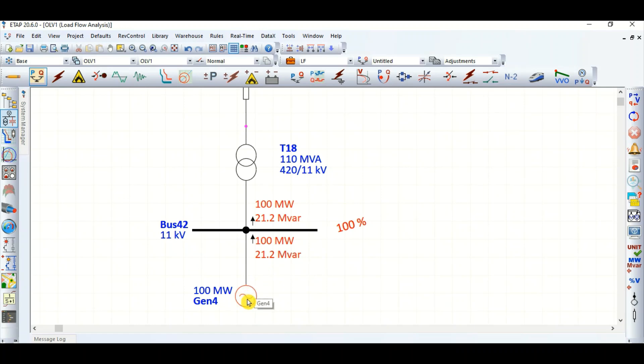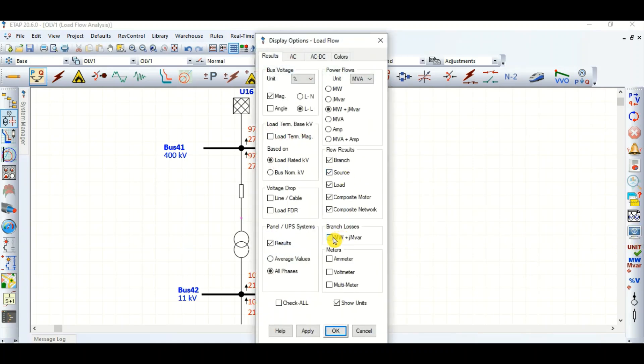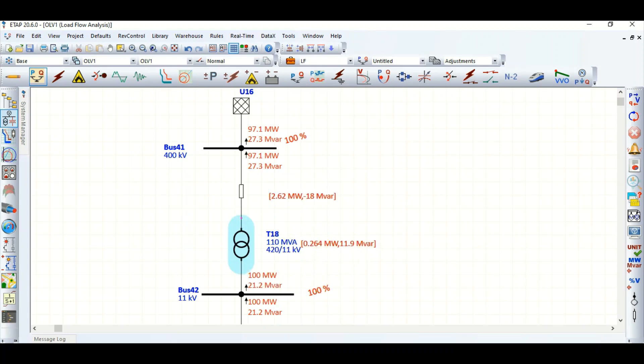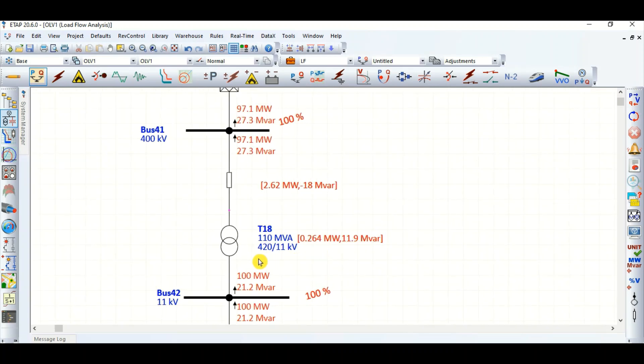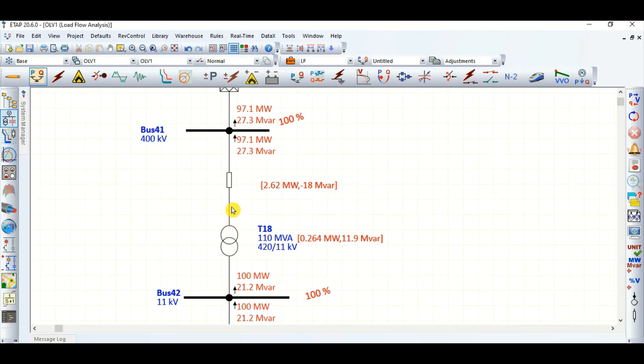Now the generator is supplying 21.2 MVAR reactive power towards the grid. If we consider the branch losses, there is a transformer loss of 11.9 MVAR inside the transformer. But the generator is supplying 21.2 MVAR, so the balance — 21.2 minus 11.9 MVAR — is being supplied after the transformer.